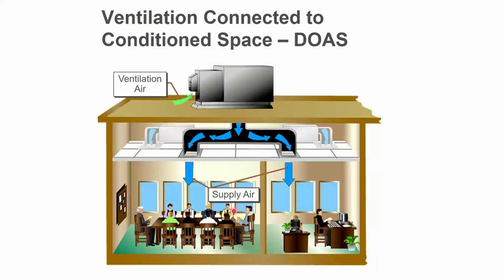There's ways to couple this guy to the HVAC equipment. I could have the ERV be standalone. This one's ducted into the space. There are separate air handlers and fan coils that heat and cool the space. My fresh air goes to the ERV and I dump it into the space. That's fine. You can do that. This is common with ductless and VRF. The only problem with this is that dumping 50-degree air on someone or 80-some degree air on someone, which is what I'm going to get from the semi-conditioned effect of the wheel, it's not very good. So I'm going to want to do something different than that.